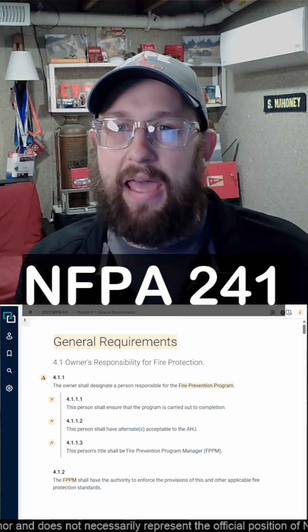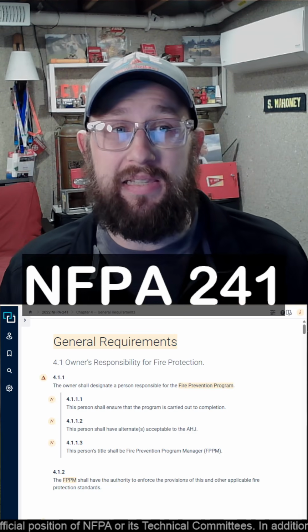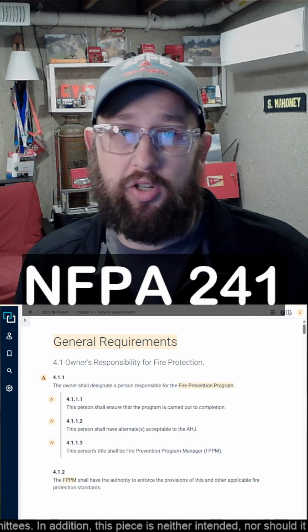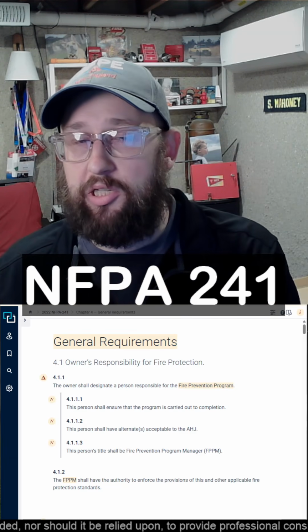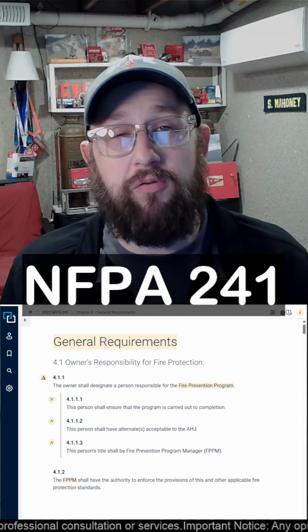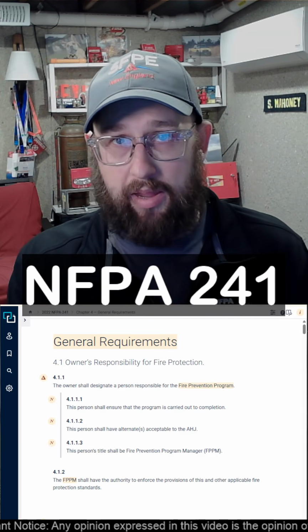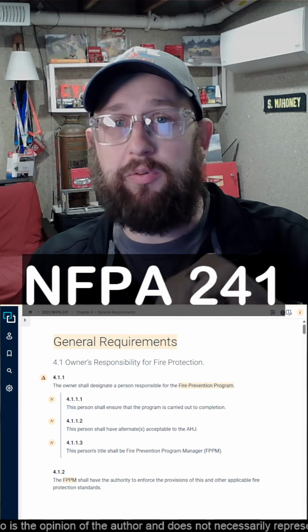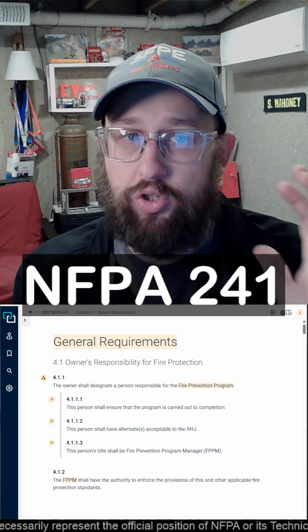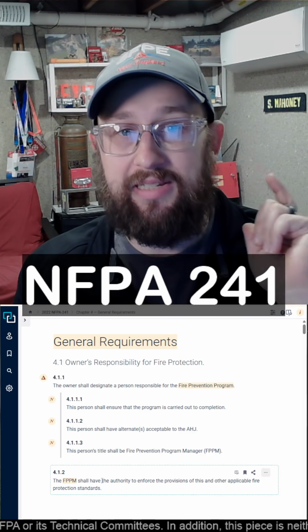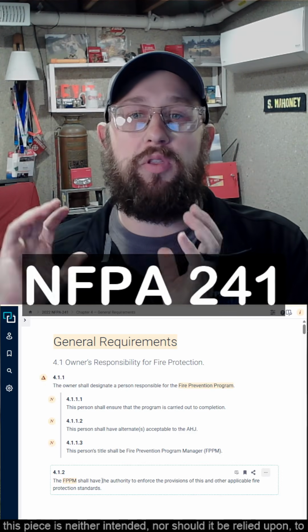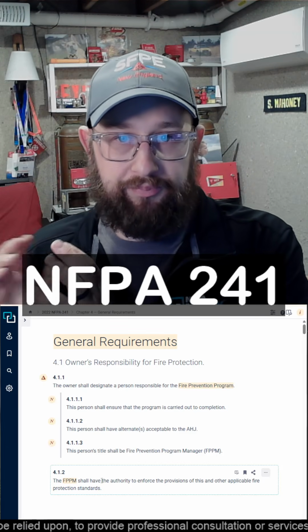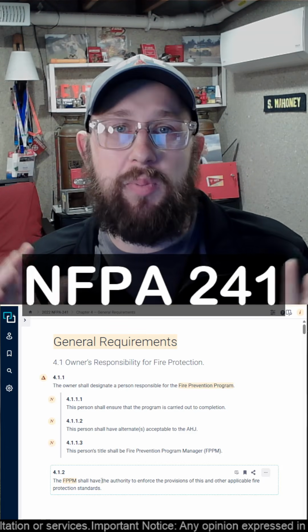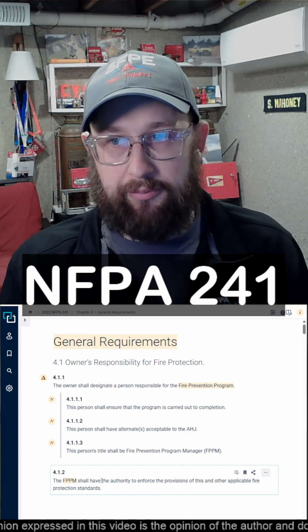The main way that NFPA 241 addresses safety in buildings under construction, alteration, or demolition is the requirement for a fire prevention program. Now, if we look below in Chapter 4, General Requirements for 241, the owner needs to designate a person responsible for the fire prevention program. So it's ultimately the owner's responsibility to make sure that this is happening.